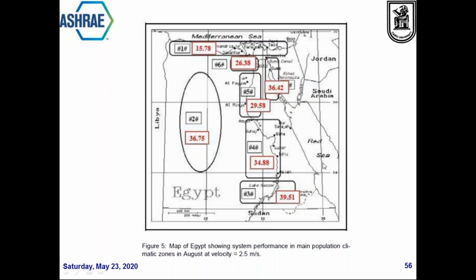We are still at the beginning of our investigations. Currently, we are doing different designs of heat exchangers, different materials, different nozzle diameters, but in all cases, we are focusing on recommending equipment and material that are locally available, that are not expensive, that will be cost effective. Because at the end of the day, we are going to design and manufacture an additional section to the air handling unit that will reduce the energy consumption by increasing the energy efficiency ratio and so on, reducing the carbon that is being used.